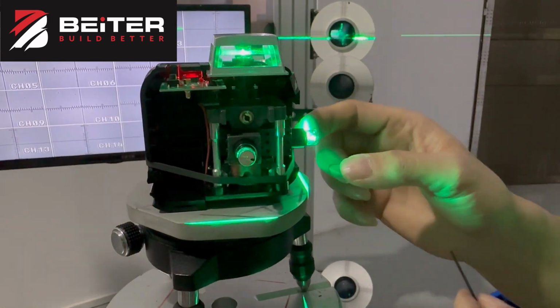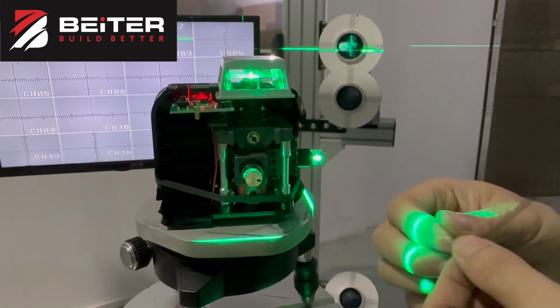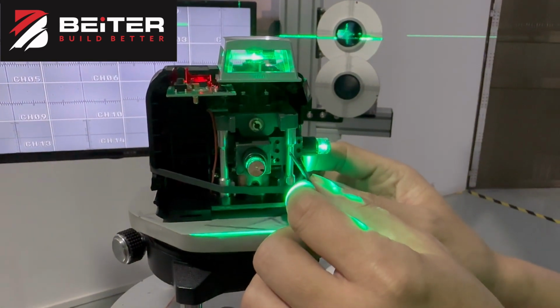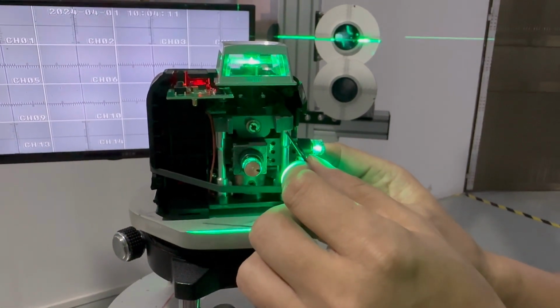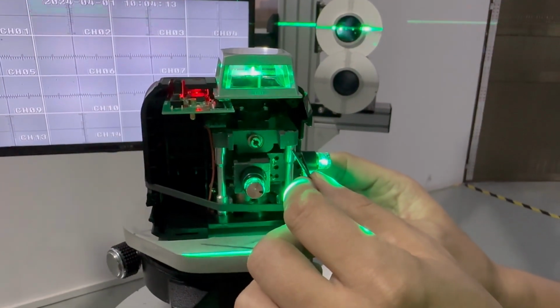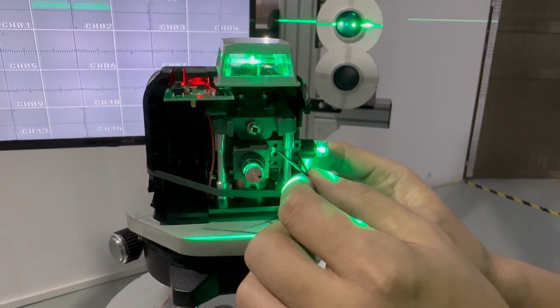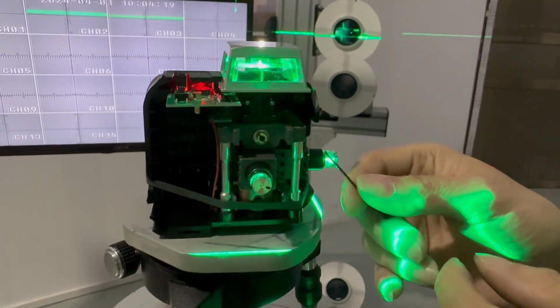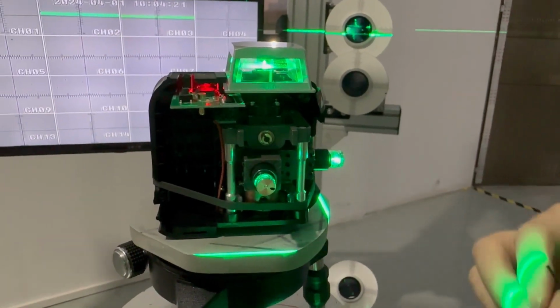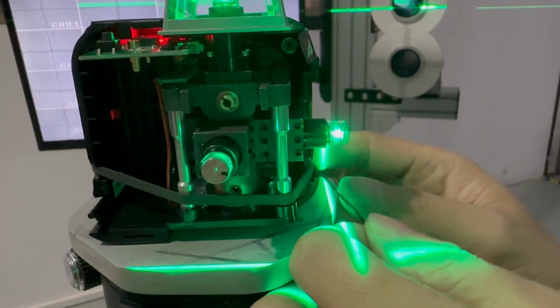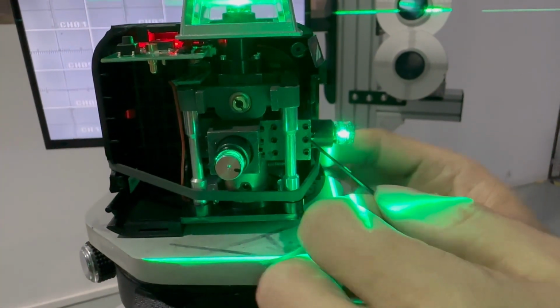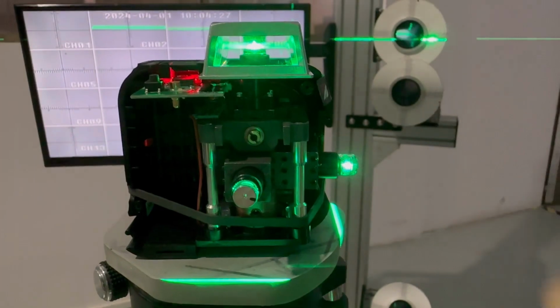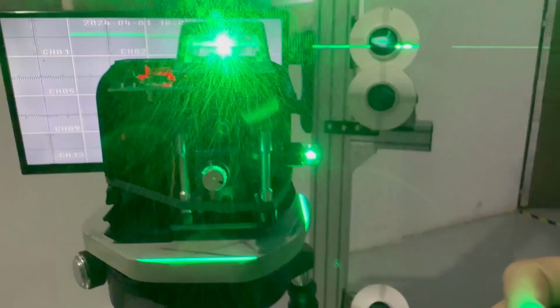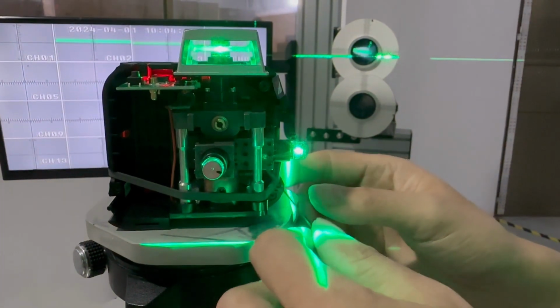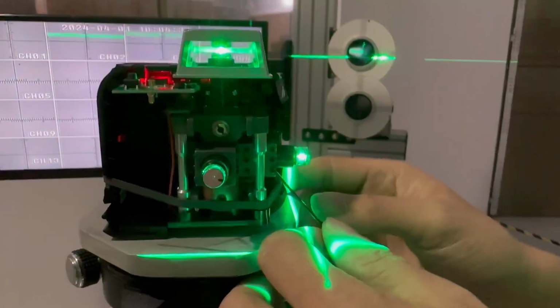Here, we're looking at the front vertical dial now. You'll find the calibration screws on each dial. Here you see 3 of them. Remember, the top and bottom screws adjust the beam's left and right orientation. The center screw adjusts the beam's direction overall. Use these screws for precise calibration for vertical beams. We'll show you how to make these adjustments step by step to ensure your SWAY-3DG is calibrated correctly.